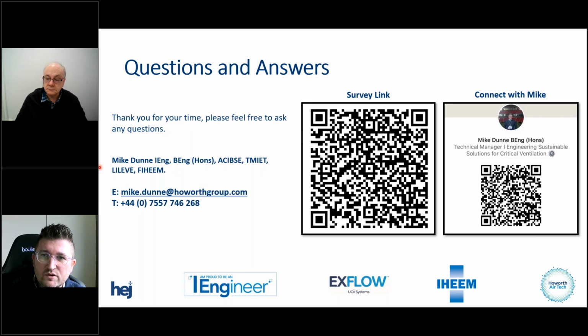Personally, from me, if you've proved at validation that with the barn design that the canopies contain and protect the patient, if one pod trips, we still achieve the room pressures, we still achieve the dilution air change rate to a percentage that's acceptable to HTM, I would just go through the servicing of the UCVs as you would service a normal operating theatre to control the capital cost on that one, and then maybe every couple of years go back and do that cause and effect. But if you've done it at day one, in my opinion, it would be a waste of money. But your authorising engineer may see that different, your ventilation safety group may see that different. That's just literally my opinion.